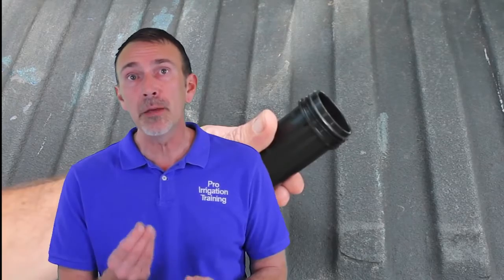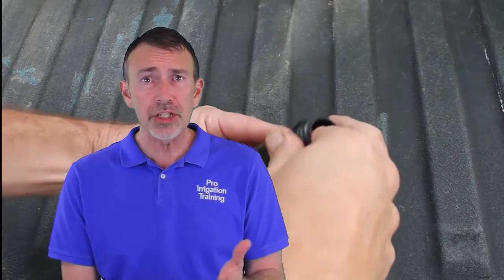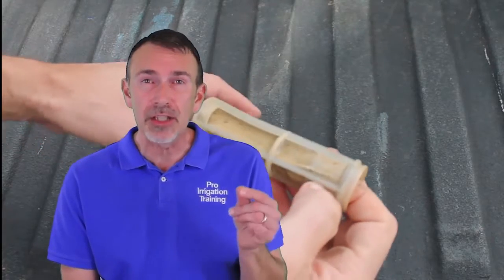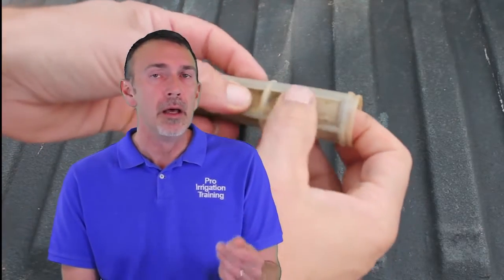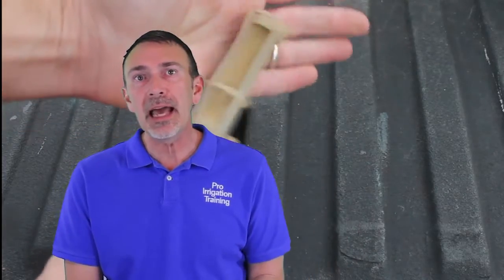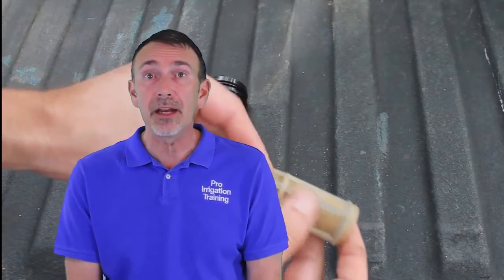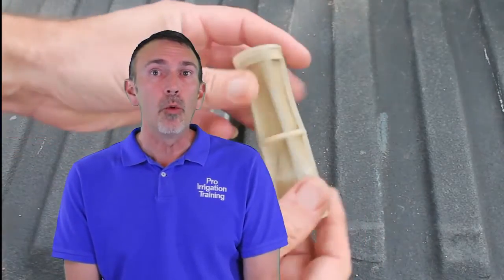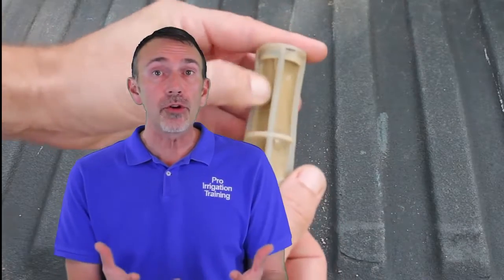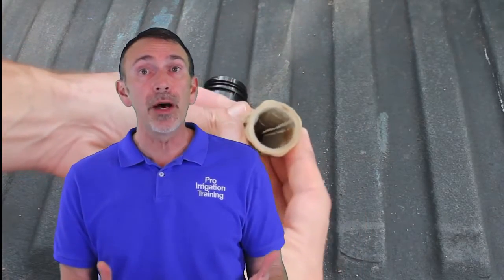Wells. Wells around here are pretty popular. In some areas of our state, we have a moderately low water table. So it's easy to use a well to pull water up from the ground. But a lot of times you get sand that comes from the bottom of these wells, whether it's just regular sand or that micaceous sand that looks a little shiny when it comes up. You can definitely tell that this stuff will get down in the heads or the drip emitters in this case and clog this stuff up. So we definitely want a filter or multiple filters on the system, but we also need a maintenance plan on how we're going to flush these filters and clean the screens out.